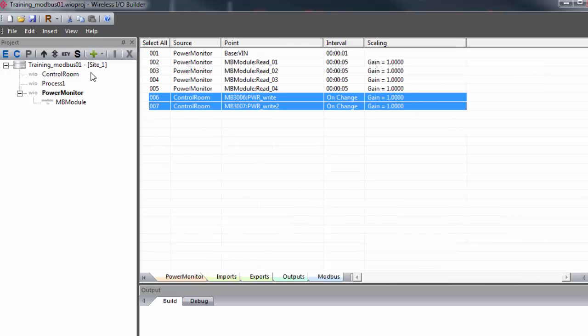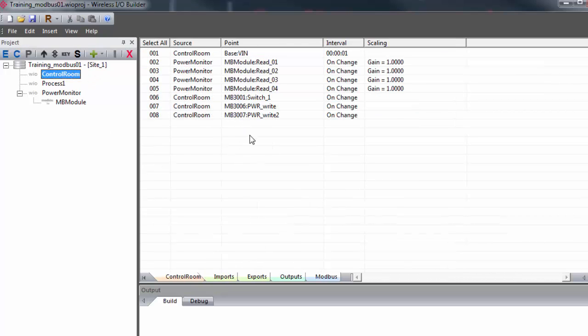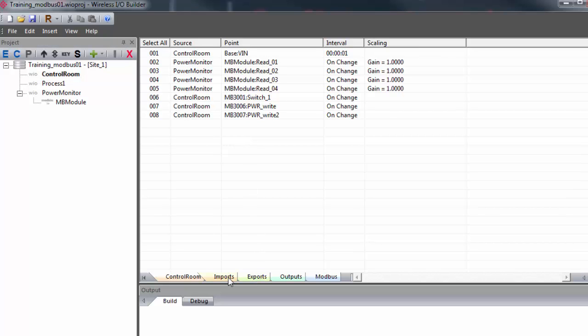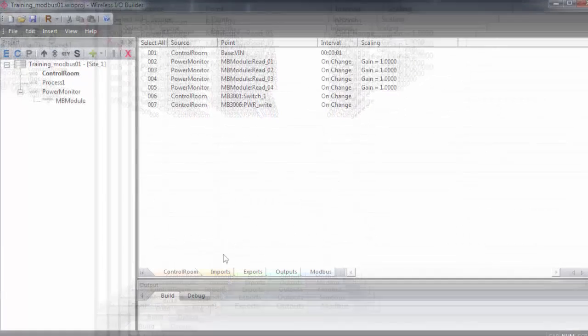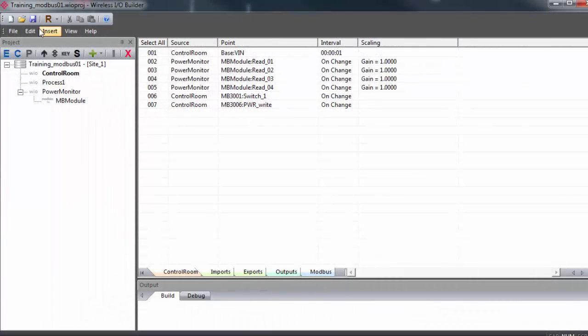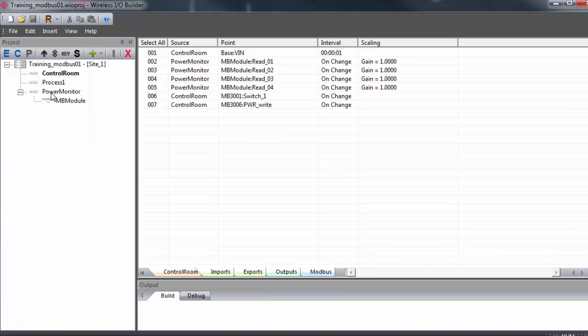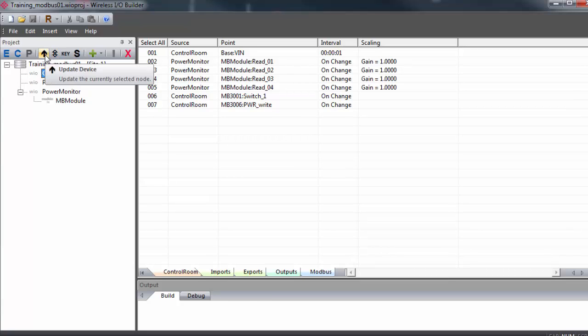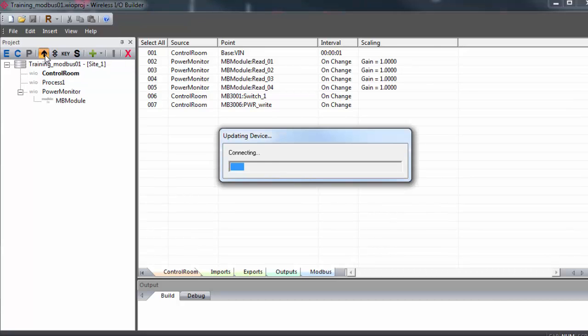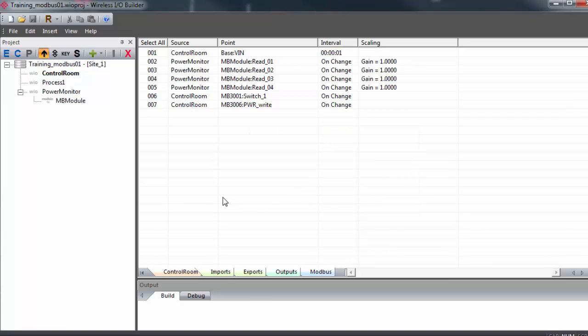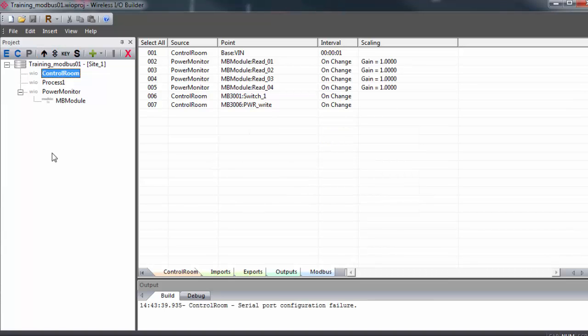Now all the Modbus read and write registers have been assigned. With our configuration set and our points mapped, we want to save this configuration file. Then with your computer plugged into the config port on the front of the primary gateway, we'll double click on the primary gateway in the tree view and hit update device. This will send the configuration to the gateway. We'll get a progress bar that lets us know when the update is finished.